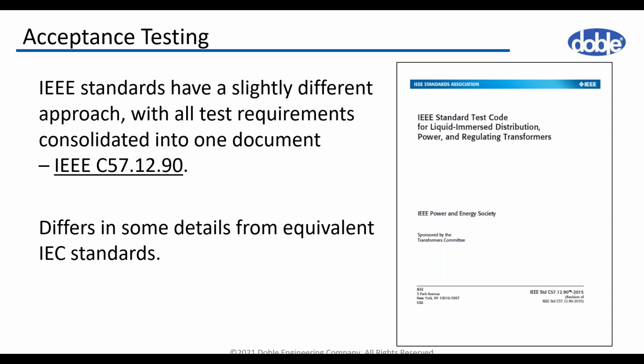Another family of standards which could be applied for power transformers are IEEE standards. It has a somewhat different approach in comparison with IEC, and all requirements for the tests are listed in a common document, which is IEEE C57.12.00. And there is only one more companion standard to this one, IEEE C57.12.90, where you can find the methods for performing the tests. I cannot say that both standards, IEC and IEEE, are very different, but they differ in some specific areas.